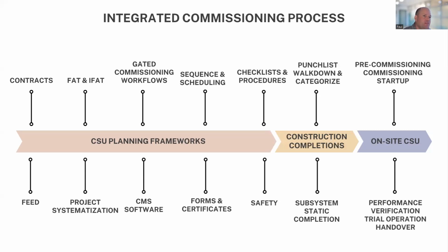The second framework for construction completions is our subsystem static completions. I mentioned earlier that everybody's definition of done always seems to mean something different. When this is properly defined in software for each specific subsystem, everything required for every tag, every physical piece of equipment, as well as all documentation, red line drawings, protection coordination studies, anything required, is explicitly defined and itemized in your commissioning software. So everyone has a crystal clear picture of what each static completion is and how to achieve that goalpost so nothing gets missed. This is critical to make the transition from construction to commissioning much smoother because everybody has visibility on what's required.